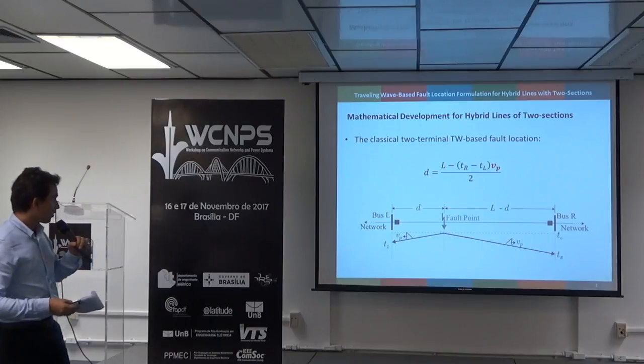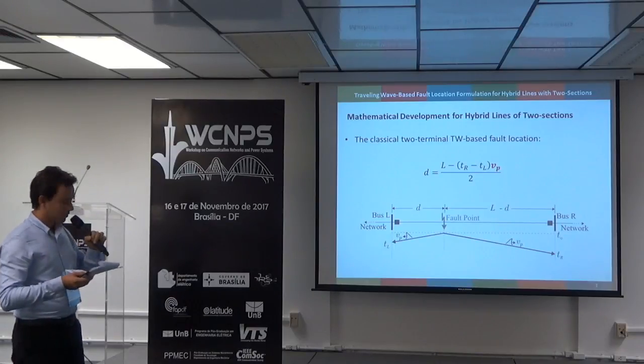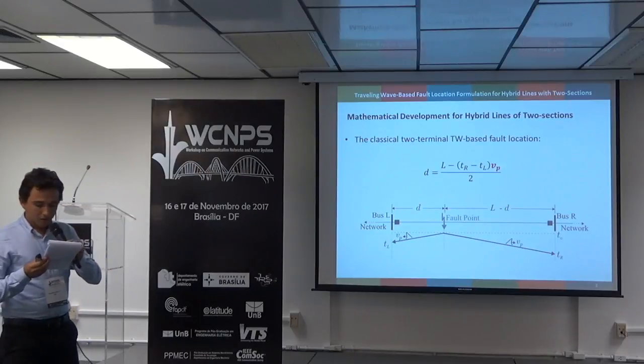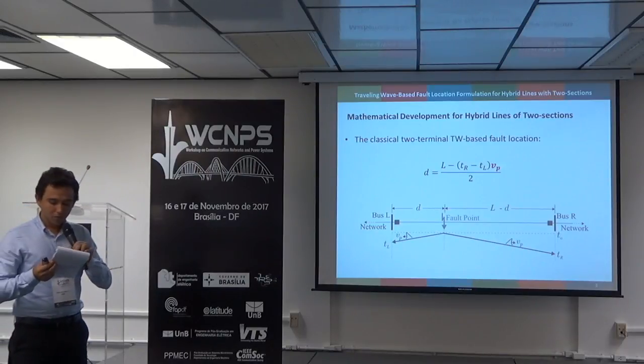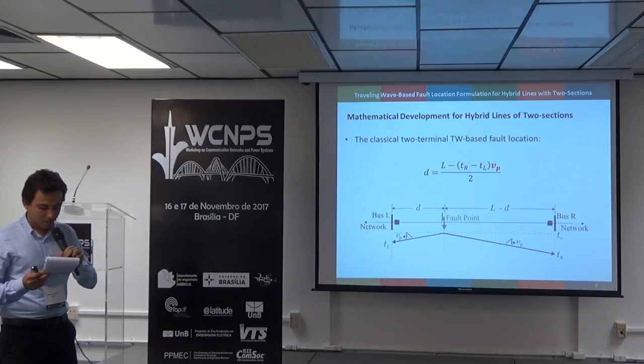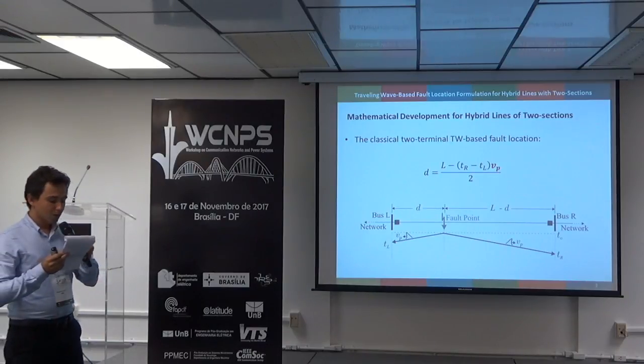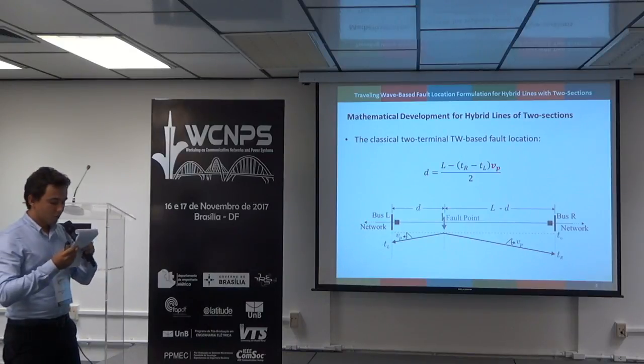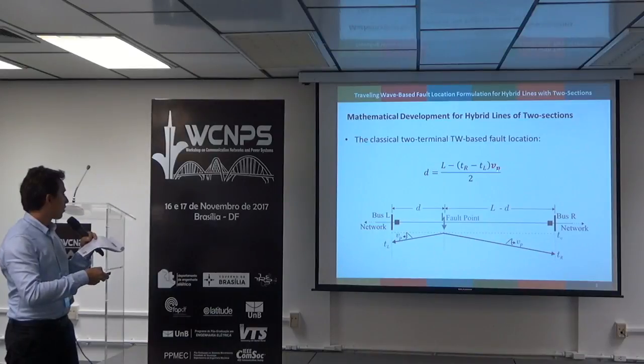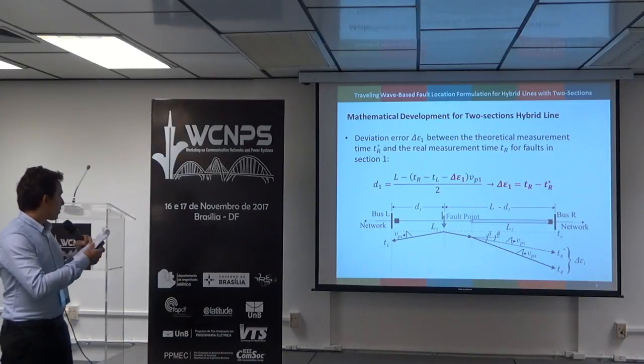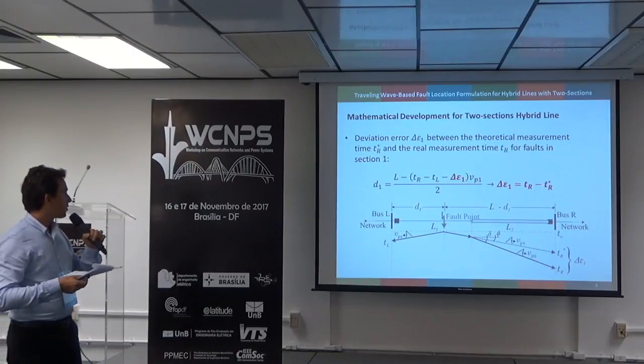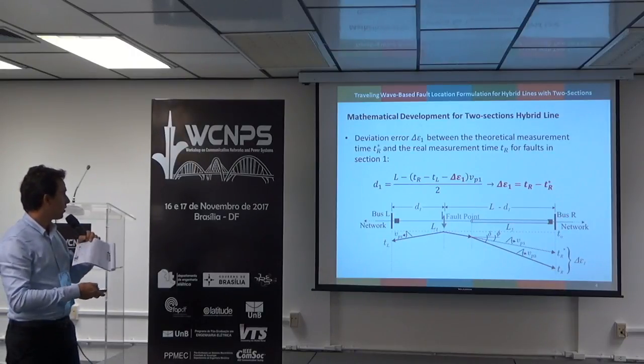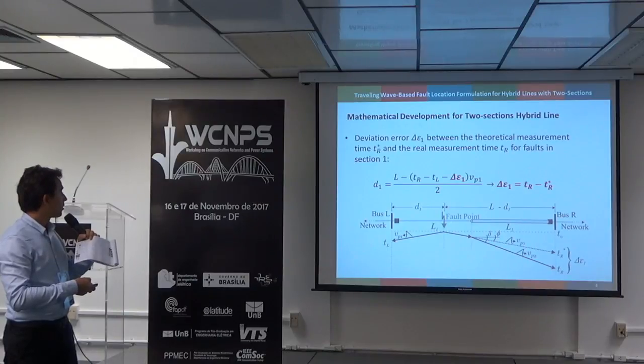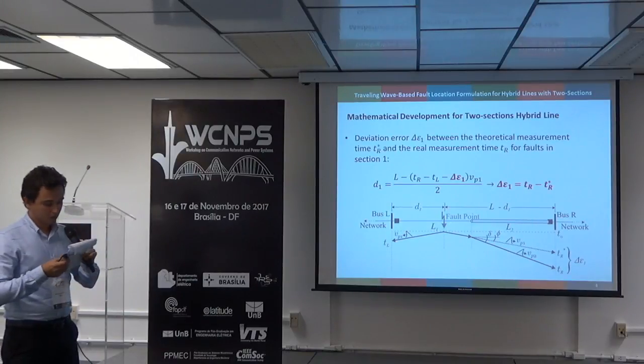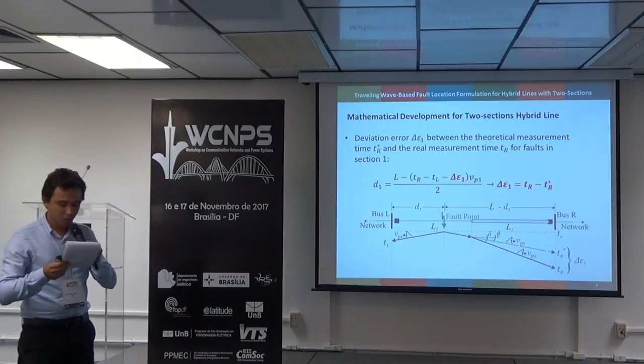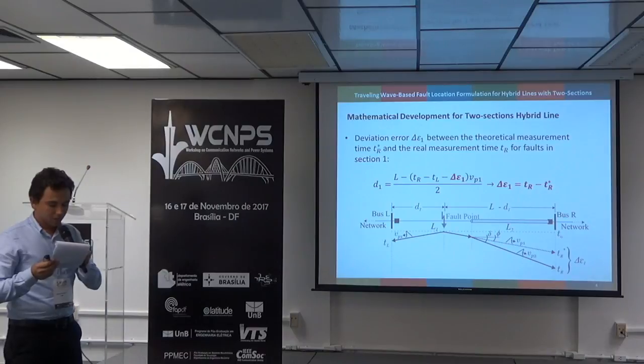So the mathematical development derives from the classical two-terminal traveling wave-based fault location. In the classical formulation, the line propagation velocity is considered uniform and constant along the line. But in a hybrid transmission line, we have two sections with two different velocities. So this application is not appropriate for faults in this kind of line.